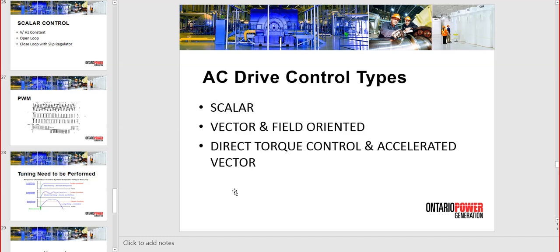it will be a must. So vector control is a must. An alternative in the case of the fueling machine is to use the servo. Servo is always vector and torque, so every servo system will automatically incorporate a vector system and a direct torque control system, and will not have scalar. So scalar is not part of any servo system, but the other two are there by default.